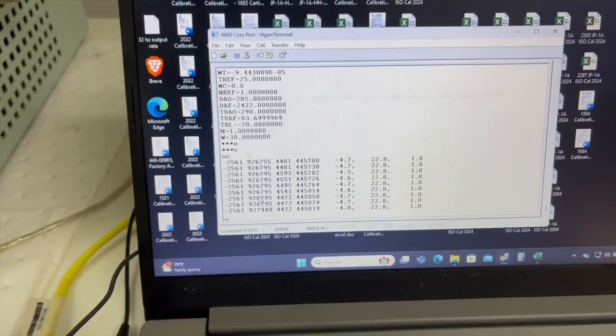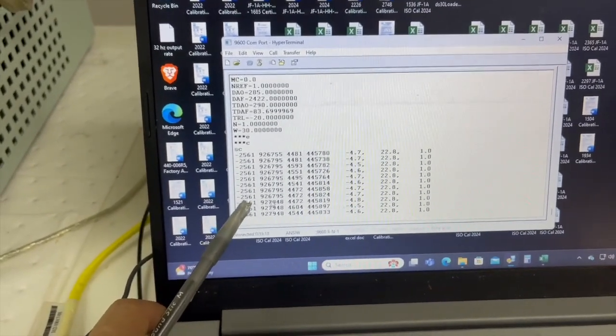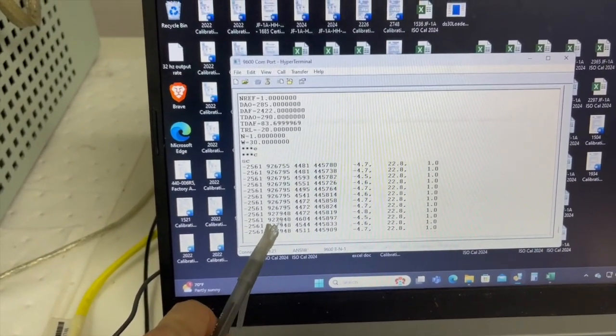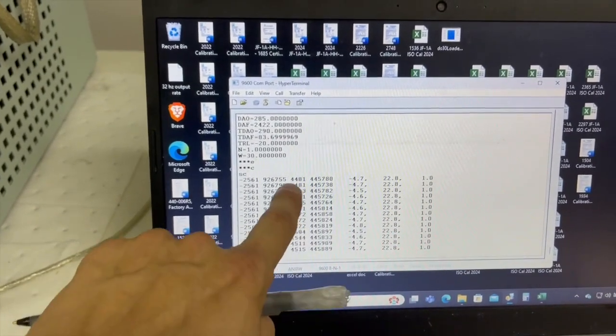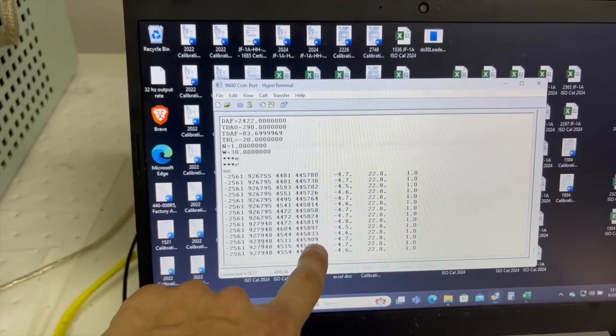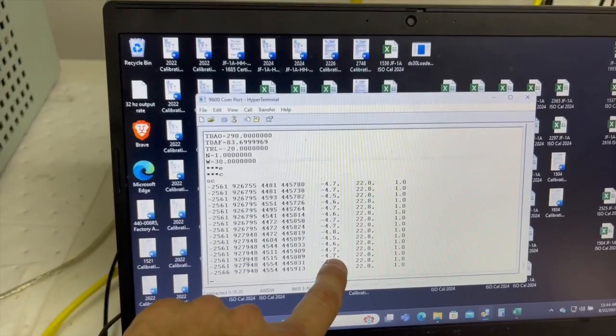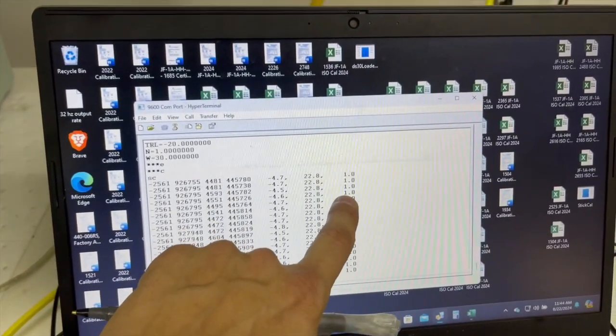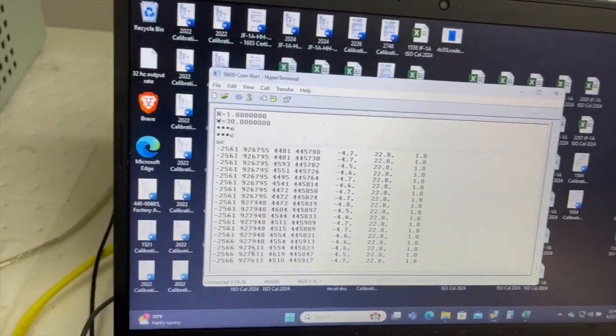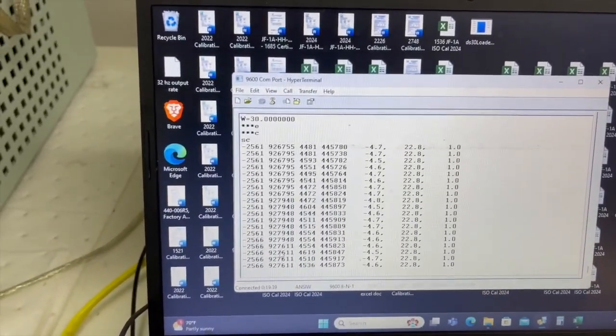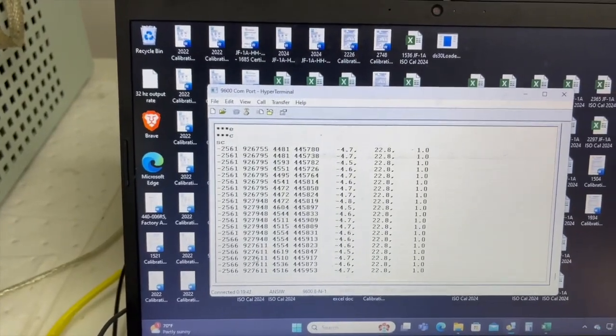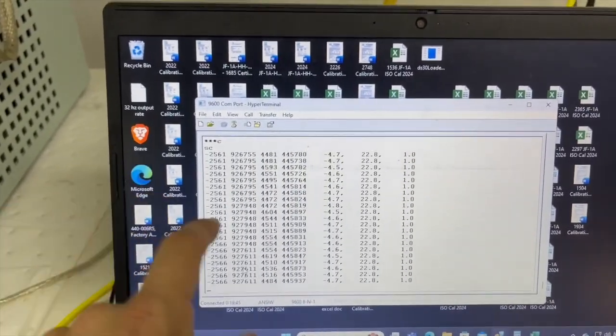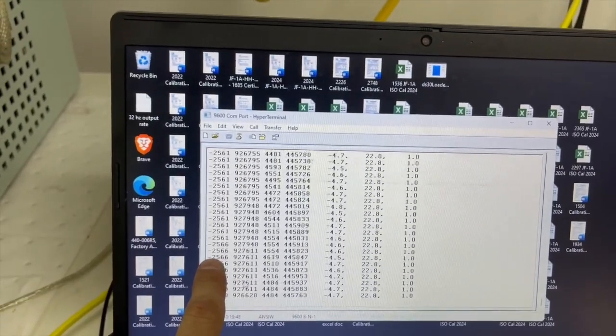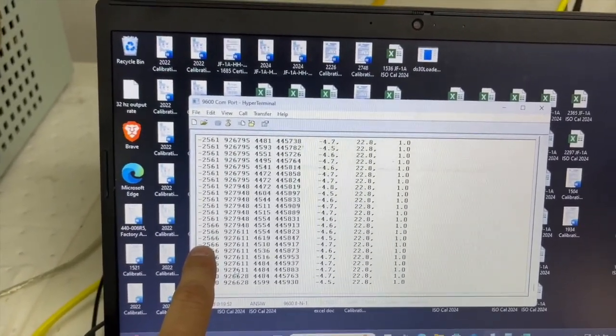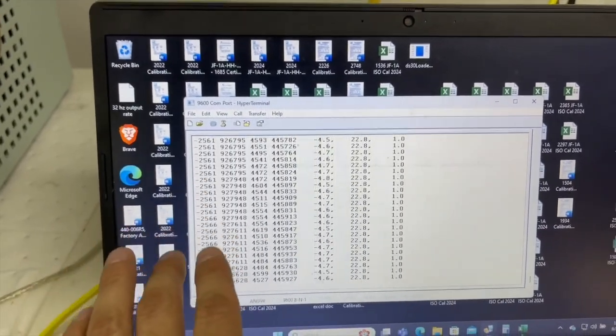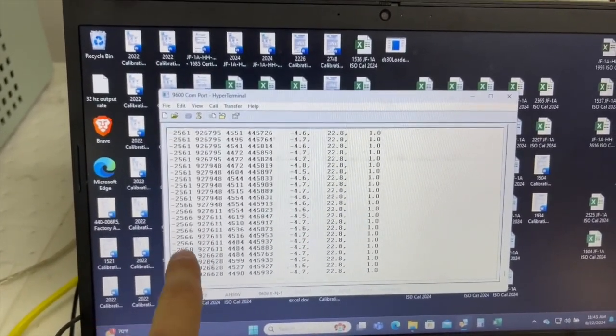Okay, so once you've done that, you have your zero counts, your sensor counts, your conductivity counts, your temperature counts, and then this is your conductivity, temperature, and compensated conductivity from the run screen. So now you're just seeing these other ones in front of it. I'm going to take down all that information. Your zero counts, this first column here, should be between minus 15,000 and 15,000 right now, without anything going on. As long as that's the case, that's good.